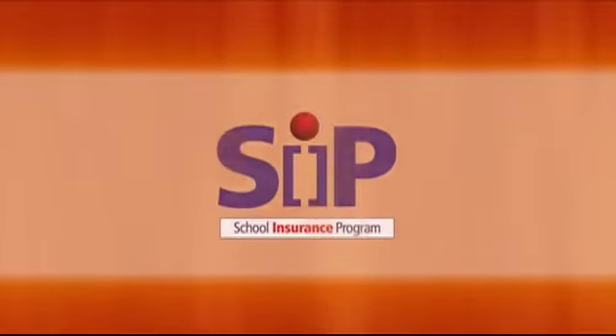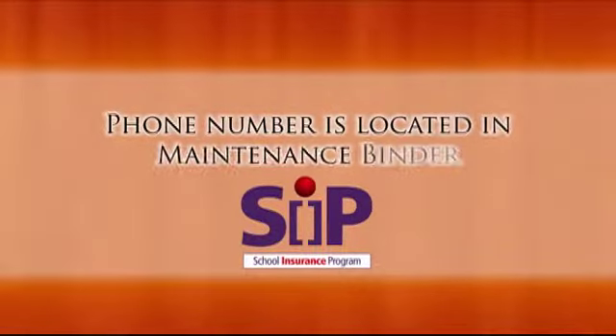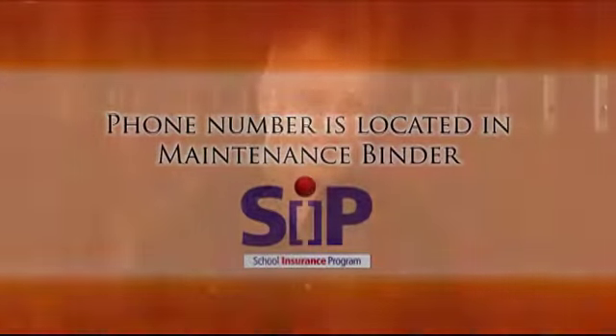You must notify the Nova Scotia School Insurance Program, or SIP, of all interruptions in any fire protection system. The number is in the maintenance binder. Now, simply leave a message with your name and phone number, the name of your school board, the name and address of the location, and the length of the interruption. Indicate which system is being shut down, such as the fire alarm or the sprinkler system, for example. And also make sure you call the pager and leave a message when the system is back up and running again. Now, the fire department must be notified if the system is going to be down for more than 2 hours. And if it's going to be down for more than 6 hours, a fire watch must be organized.